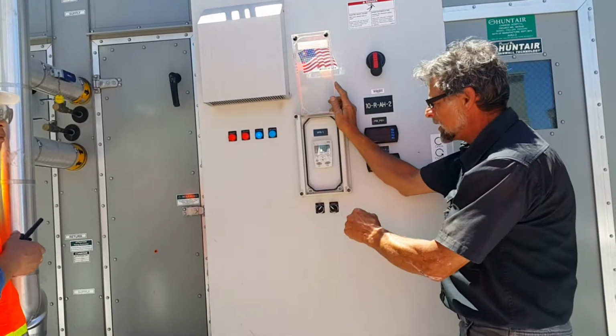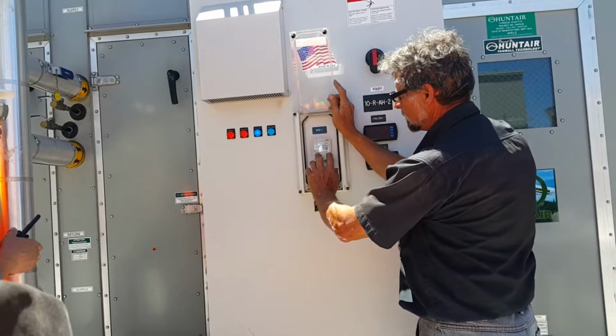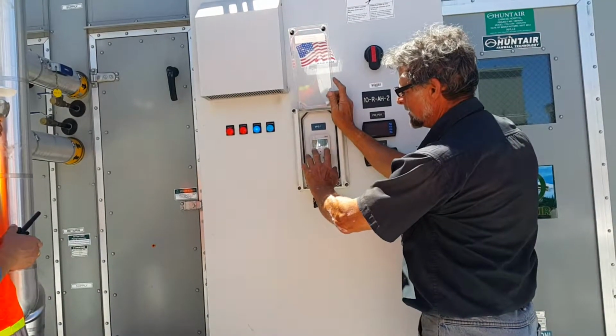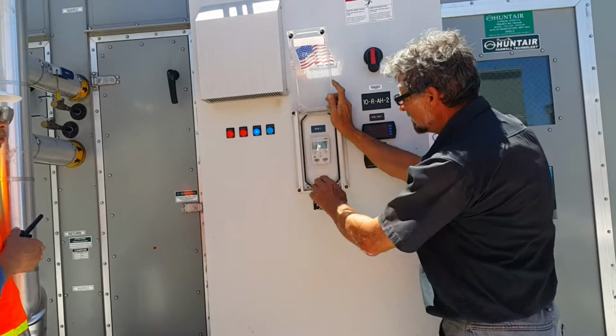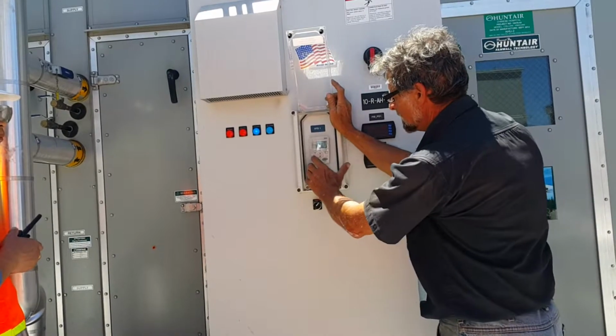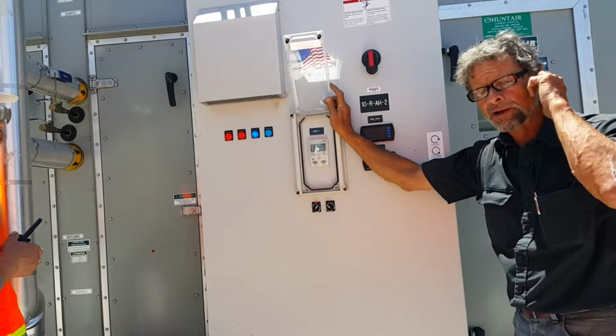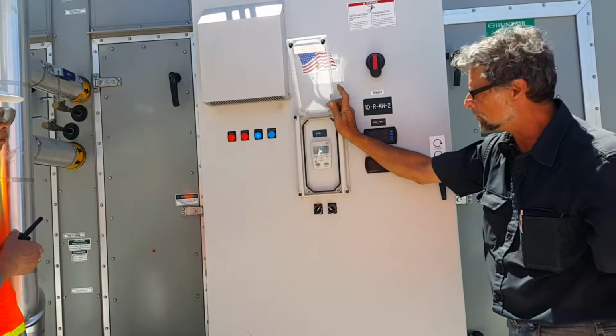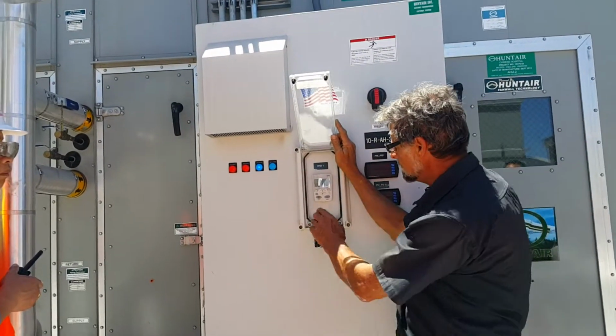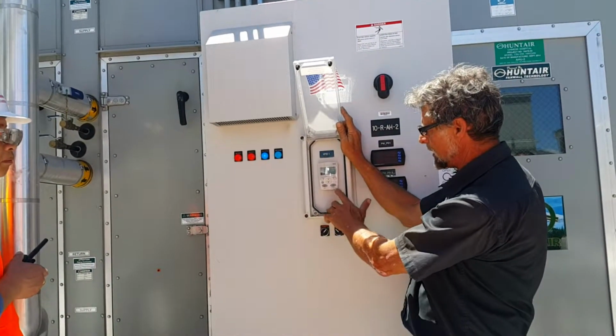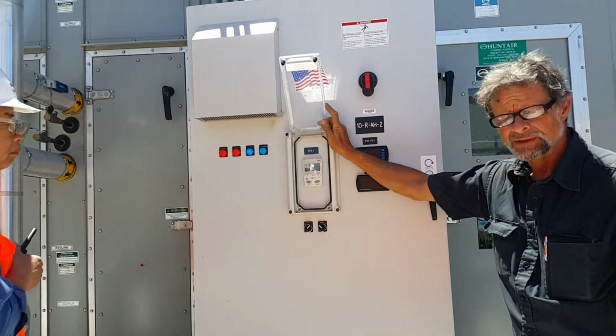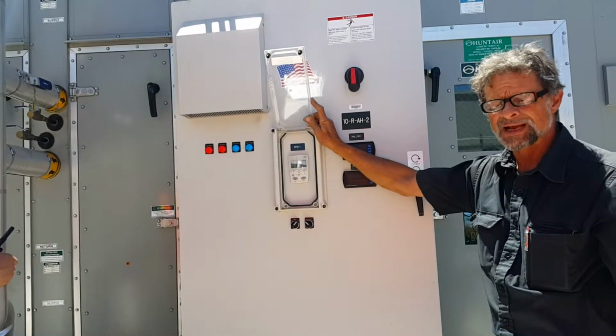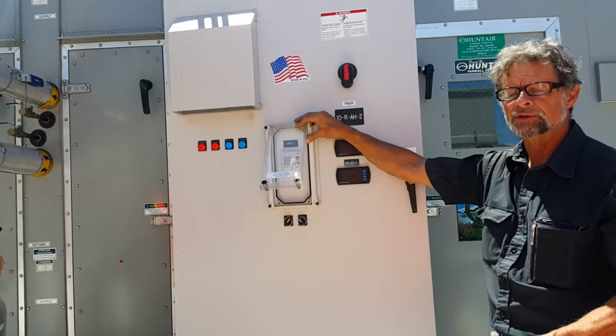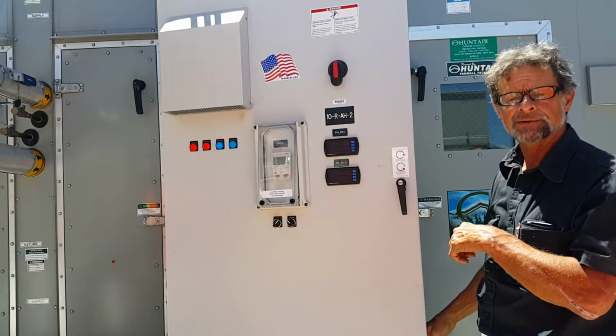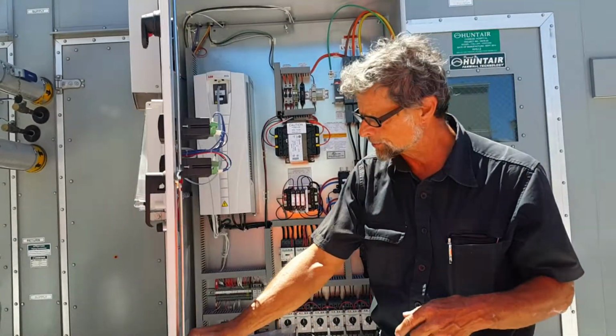So, the drive itself, you can manipulate up and down and then in and out of menus. And then there's a hand-off-auto button. The auto position is where you want it all the time for operation for the building management system. If that should fail and you need to operate it in hand, you can use the hand button. Sometimes that won't work unless the start signal is made from the controls contractor.